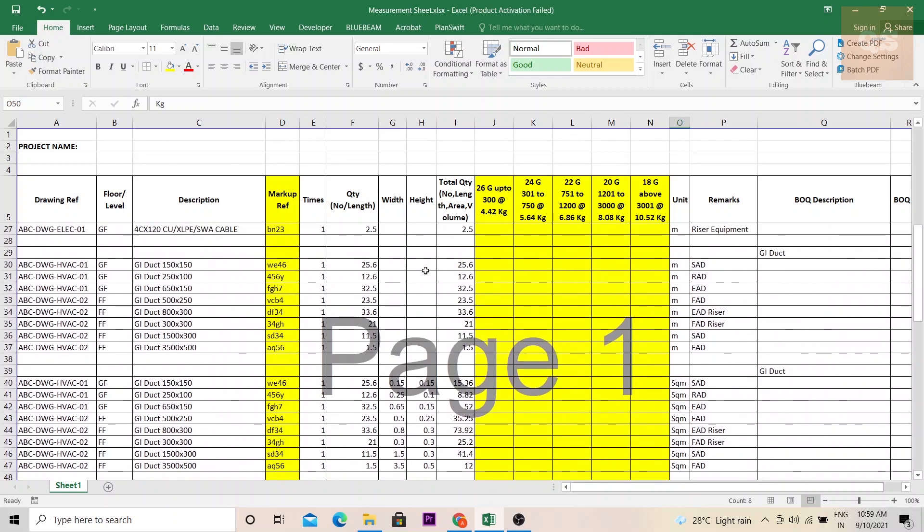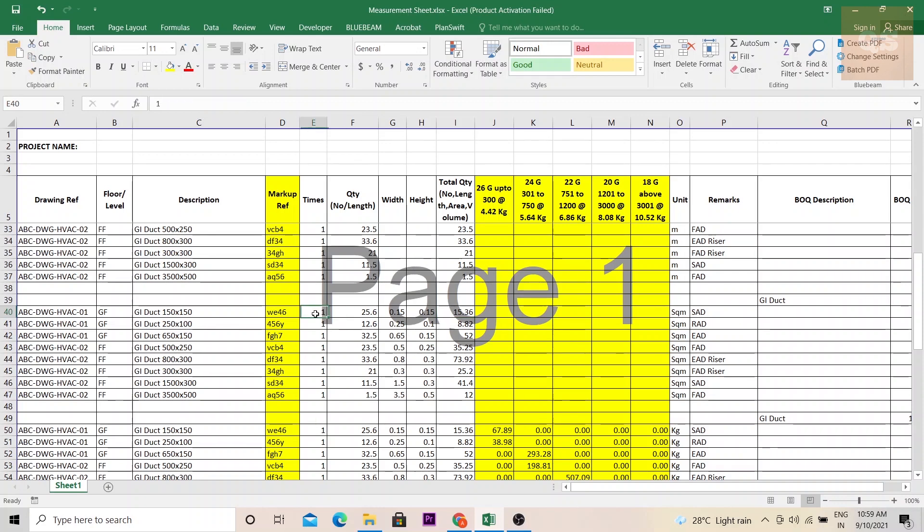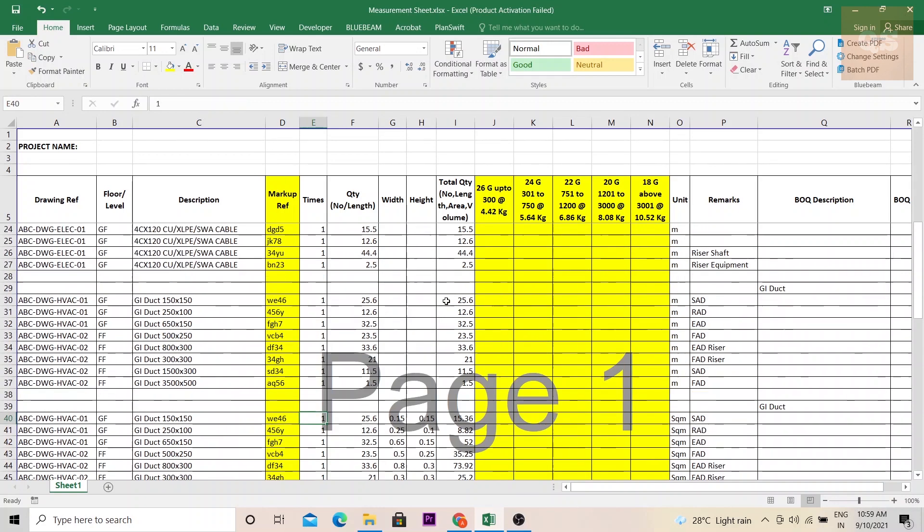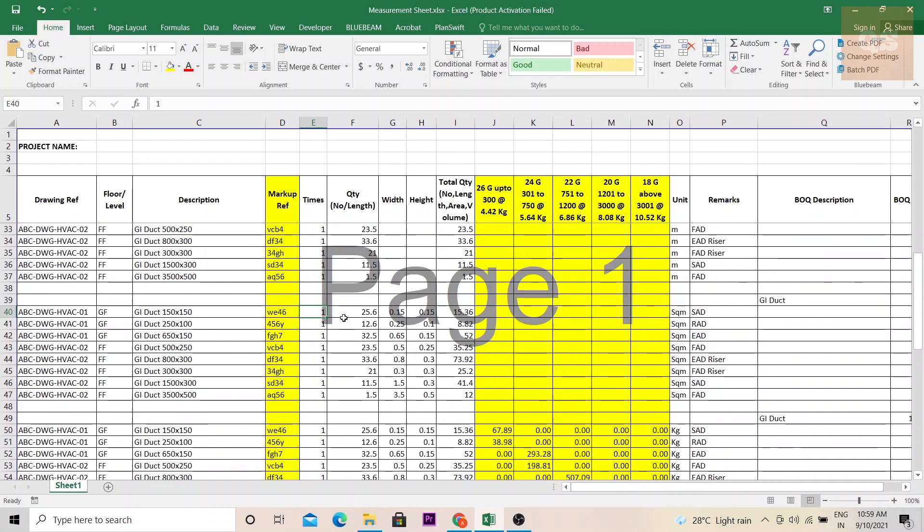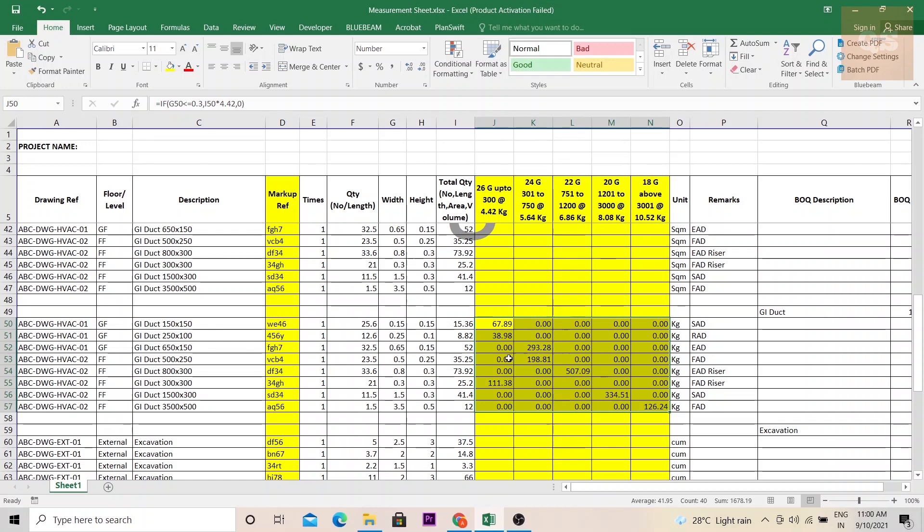If you see here this part is just in meters. Here you have included the width and height of the ducts and then the area is calculated using this formula: 2 into width plus height into length and then it is multiplied with the times also. Again as I have already mentioned if in plan it is not shown or if you are assuming a few things you can mention in the times column. Then here depending on the gauge types you can calculate the kilograms. The unit weight measurement has been mentioned.